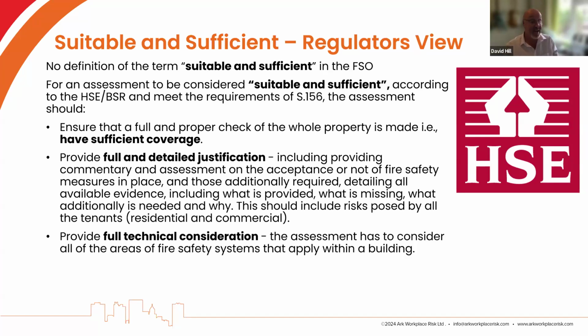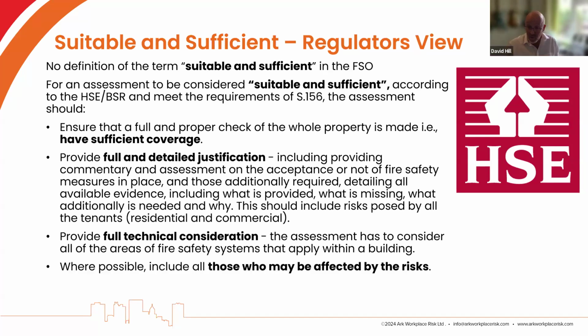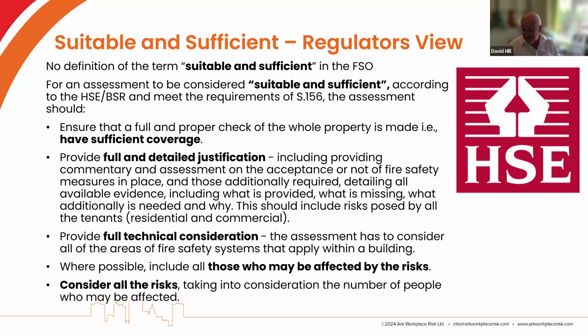It's got to provide a full technical consideration, and it's got to cover all areas of fire safety. One of the areas of concern is that a lot of fire risk assessors in the past, because they haven't had, for example, insurance, have stated, well, here's our fire risk assessment, but by the way, we are excluding the external walls. That cannot be accepted. That does not, therefore, constitute a suitable and sufficient risk assessment. So we need to make sure that all areas of fire risk are covered. And where possible, we need to make sure that those who are involved or affected by the risks are actually included within the process.